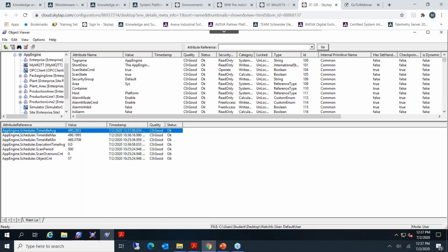This is with redundancy. Without redundancy, I need only 3, so the application object server will be only 1. Generally this is the estimation. Theoretically, any app engine can hold up to 25,000 objects, but empty objects. Here you have to ask yourself how complicated your object is. Is there a lot of scripts? Once you have a lot of scripts and complication, you have to keep in mind that this app engine must scan everything. So the 25,000 objects, not IO.